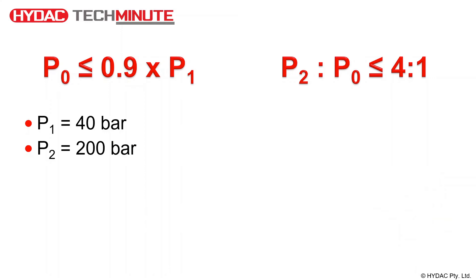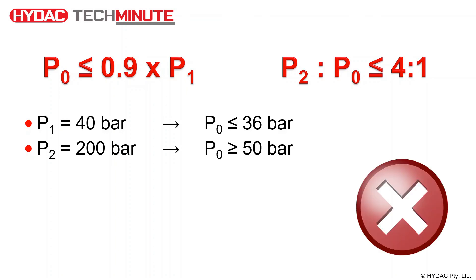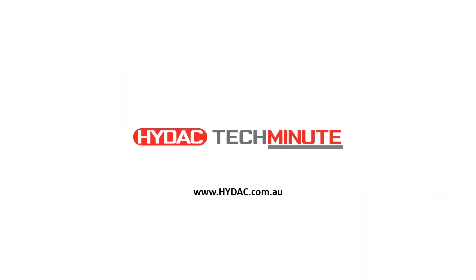Using the same method, we can determine the pre-charge pressure using the minimum system pressure of 40 bar and a maximum system pressure of 200 bar. We can see that when calculated, the pre-charge pressure would need to be less than or equal to 36 bar, but at the same time, greater than or equal to 50 bar. Clearly, this isn't possible and in this scenario, an adjustment to the minimum and maximum system pressures or change in accumulator type may be required.